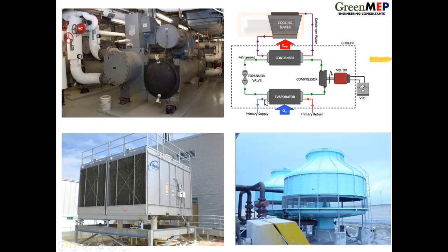Now, the chiller. A chiller is a refrigeration cycle. You know that with the evaporator, this is where the chilled water is produced. Warmer chilled water comes in from the air handling units. The refrigeration cycle works on the same principle as the refrigerator at your home. And this chiller has to maintain this temperature at a constant level all the time. If the cooling load is high, the pumps run at a higher speed, and this water will flow faster. It doesn't matter how fast or slow. This system has to maintain the supply chilled water temperature at a constant value. So therefore, there's another temperature control problem here. Temperature control problem 2, that is, controlling the temperature of the chilled water.